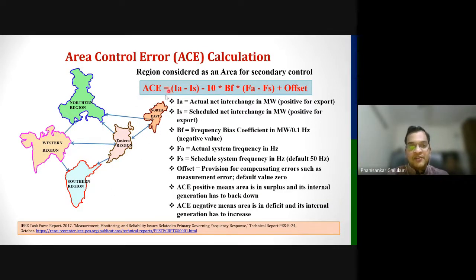One important metric when we talk about AGC is area control error, where we look at the difference between IA minus IS and FA minus FS. IA means net interchange actual minus the scheduled net interchange. FA is actual frequency minus scheduled frequency, which is 50 hertz. If actual frequency is 50 hertz and IA is equal to IS, then the offset is for compensating errors such as measurement error. Its default value is 0. So if these three terms are 0, ACE would be 0. The objective of AGC is to drive this area control error towards 0.